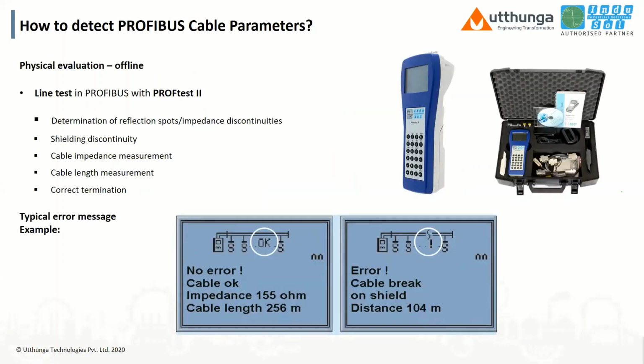So right now we understood how to detect logical and quality values, right? Even so, we need to understand what the exact cable impedance in the network is. Since the cable impedance of a Profibus network is 150 ohms, it is very important to understand whether it is in standard or not. So that's why we have the cable tester, Profi test. What Profi test does is it tests the exact cable length and finds any defects in the cable and shielding errors with the specific distance.